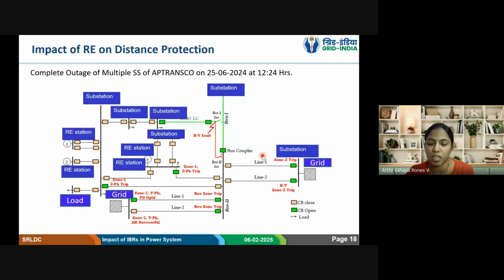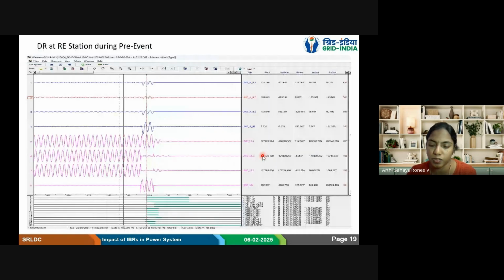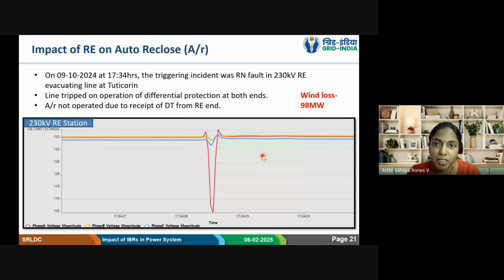So we have not observed so far any such tripping. Most of the RE connected at central level are having differential protection. Maloperation of differential protection is very minimal only. Only thing is, in case communication failure is there, again, it will come to distance. So in this case, again, coming back to the auto recloser issue, why auto reclosers are not operating in RE connected evacuating line?